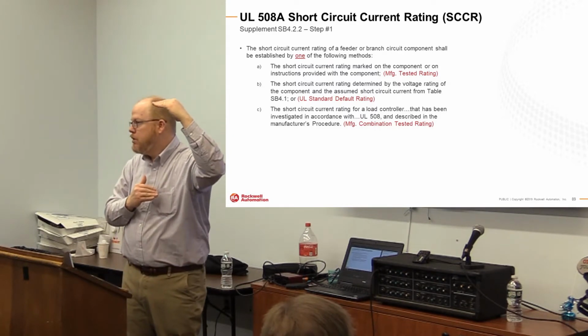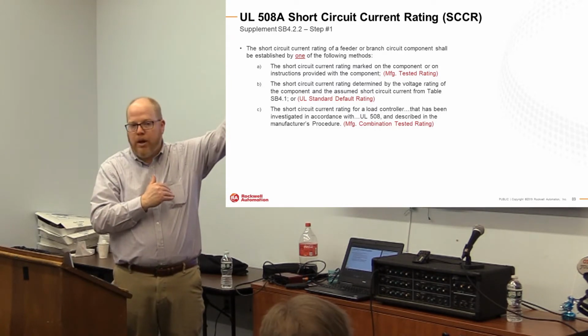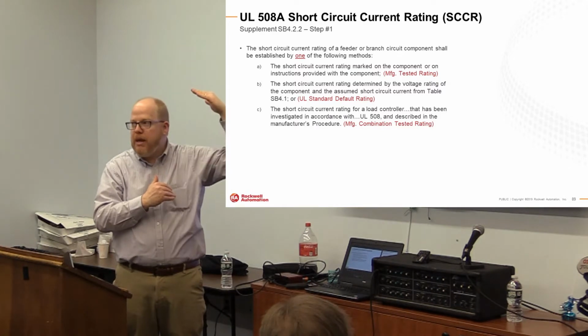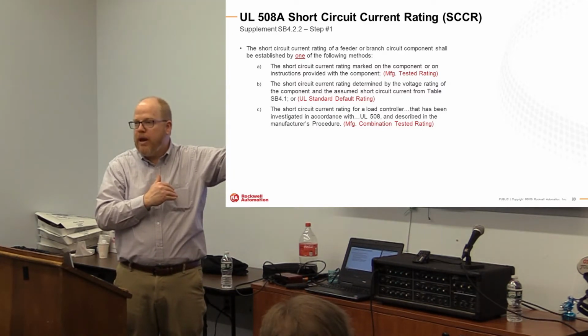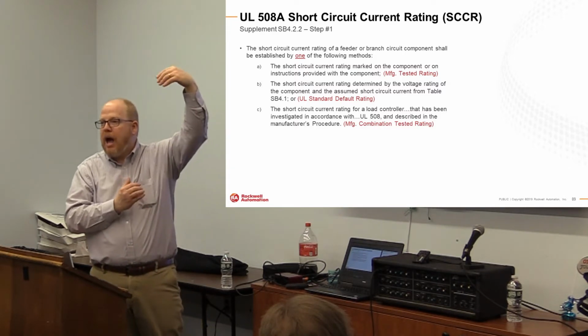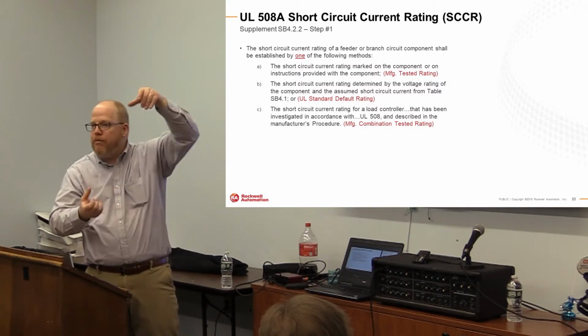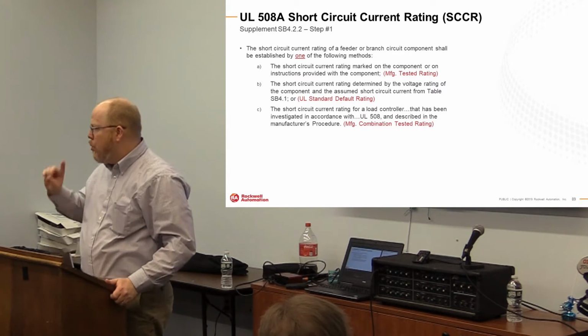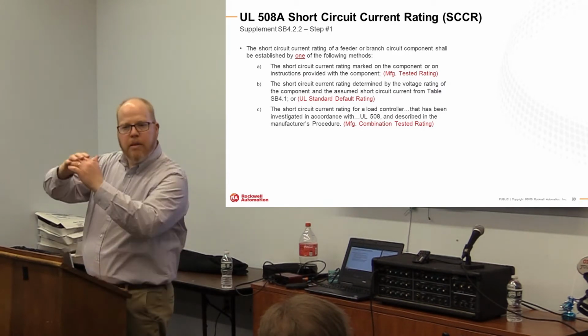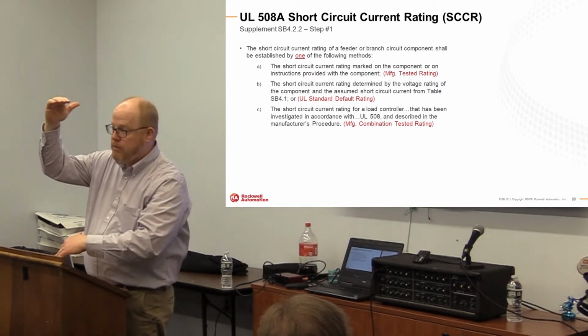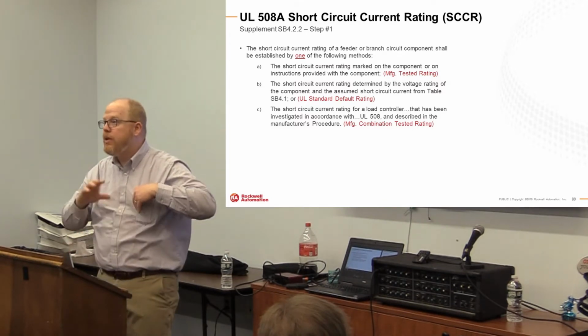So A is an individual component rating from the manufacturer. B is an individual component rating from the back of the UL book. And C is the combination rating of an assembly of components. Again, it's a one-stop calculation that might cover up to 3 devices. Okay, all clear on that? So that's step 1. It's one of those 3 choices.